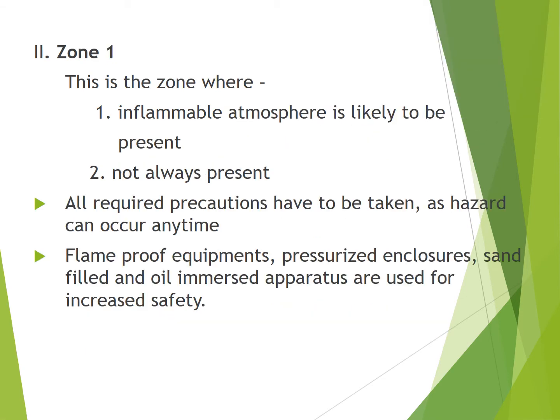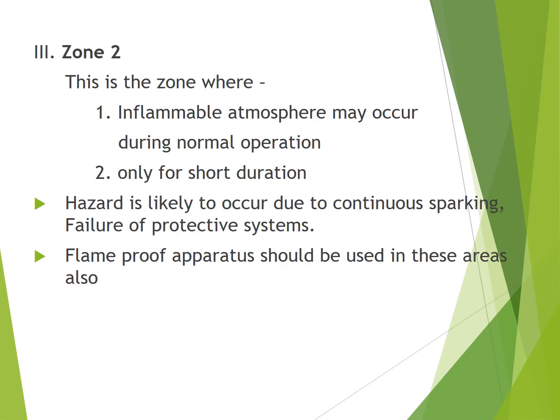Zone 1 is a zone where an inflammable atmosphere is likely to be present sometime, but not always. Since a hazard can occur at any time, all required precautions have to be taken. Flame-proof apparatus or flame-proof equipment can be used in this area. In some places, pressurized enclosure, pressurization with inert gas or air with automatic switching off in case of loss of pressure can also be used, or sand-filled or oil-immersed apparatus can also be used in this area.